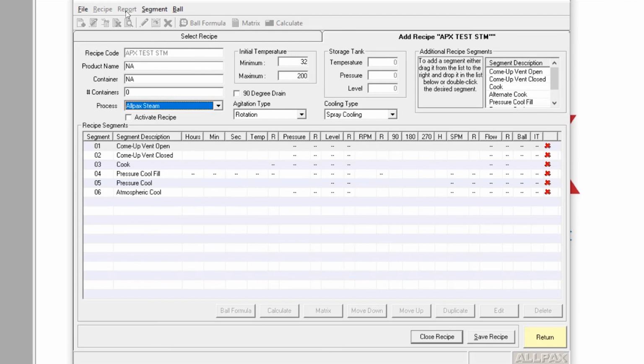So if you don't put any values there when you try and run a water spray process or a water immersion process, the machine literally won't run. The first thing it does is use the pressure in the storage tank for those processes to pump the hot water to the top tank. And if you haven't filled out a temperature or a pressure for that step, your process will not run.